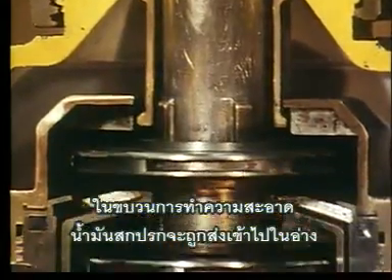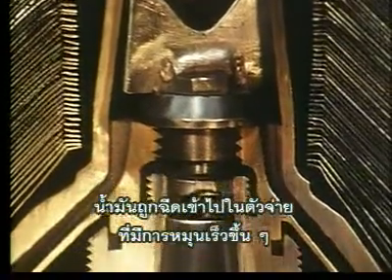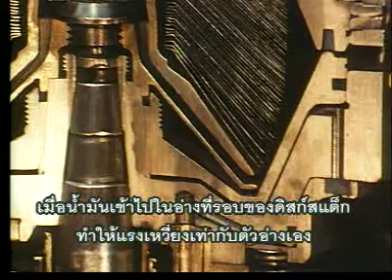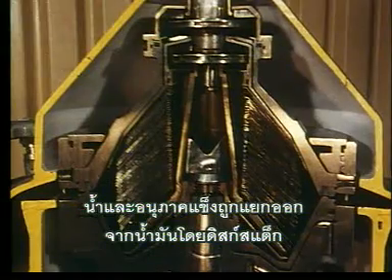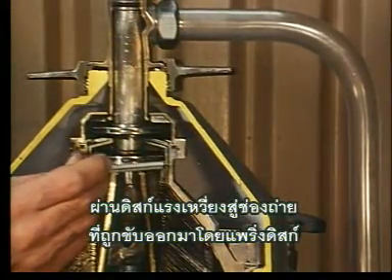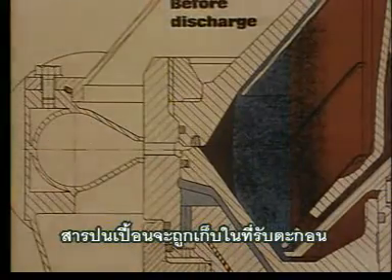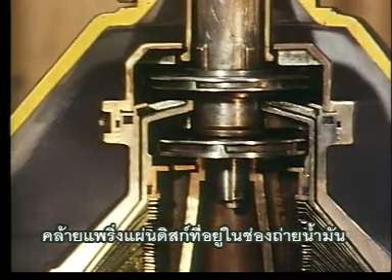In the purification process, the dirty oil is introduced into the bowl through the inlet. The oil is accelerated in the distributor to higher and higher rotational velocity, so that when the oil is introduced into the bowl at the periphery of the disc stack, it has almost the same velocity as the bowl itself. The water and solid particles are separated from the oil in the disc stack. The water flows continually through the channel formed by the bowl hood and the top disc, passes the gravity disc into an outlet chamber, from where it is discharged by means of a so-called paring disc. The particles are collected in the sludge space. The purified oil is discharged through the oil outlet by means of a similar paring disc located in the oil outlet chamber.